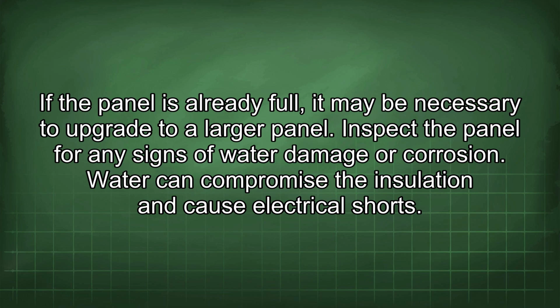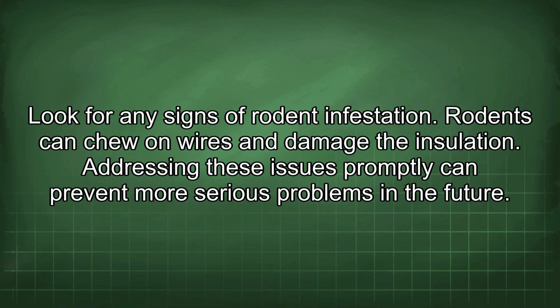Inspect the panel for any signs of water damage or corrosion. Water can compromise the insulation and cause electrical shorts. Look for any signs of rodent infestation. Rodents can chew on wires and damage the insulation. Addressing these issues promptly can prevent more serious problems in the future.